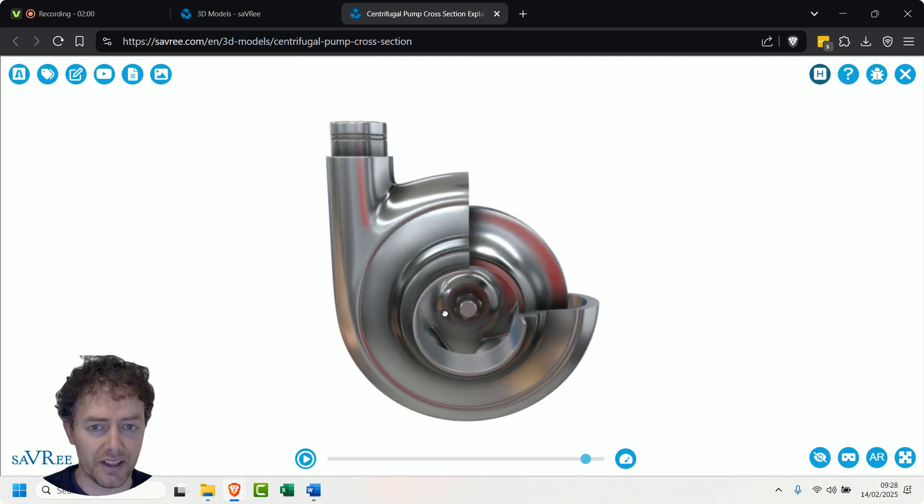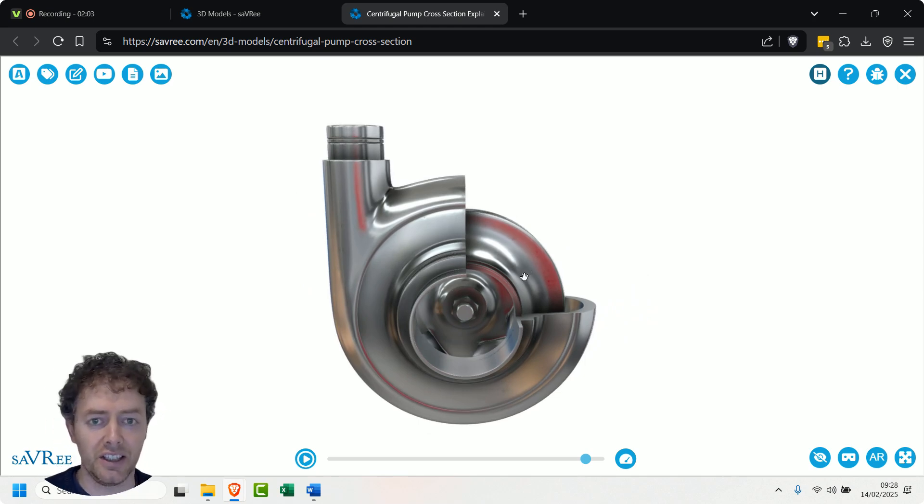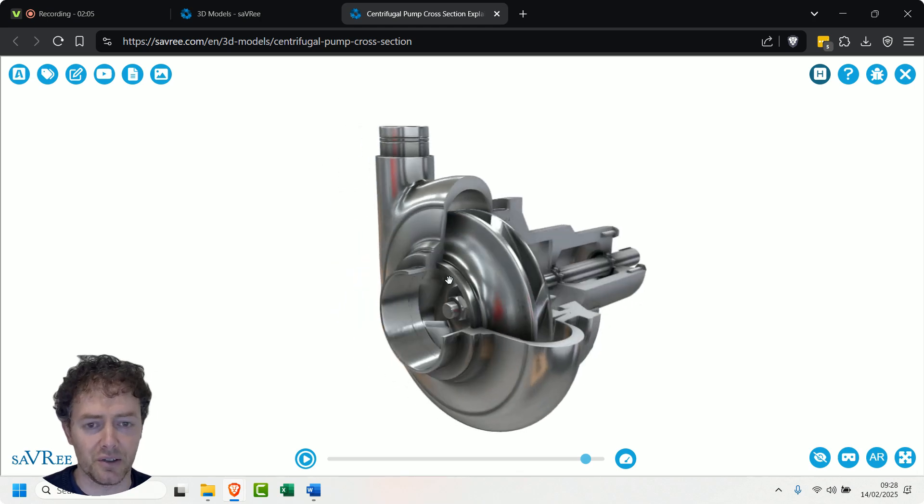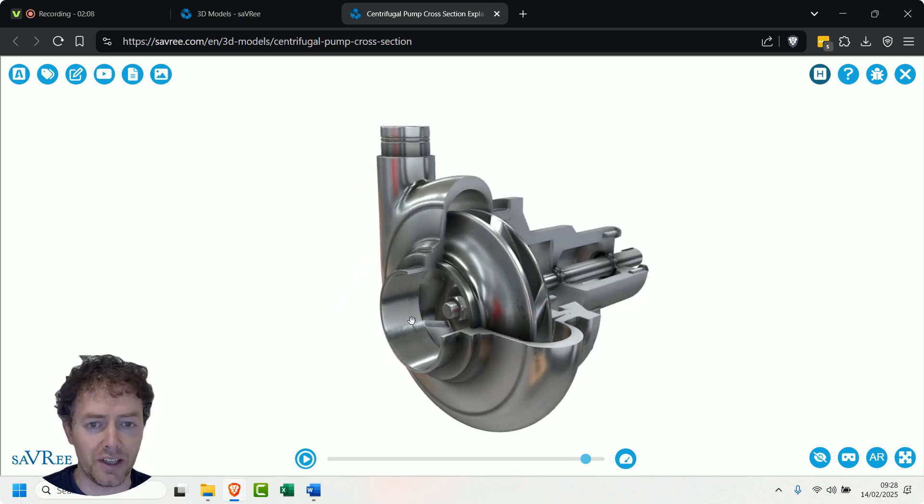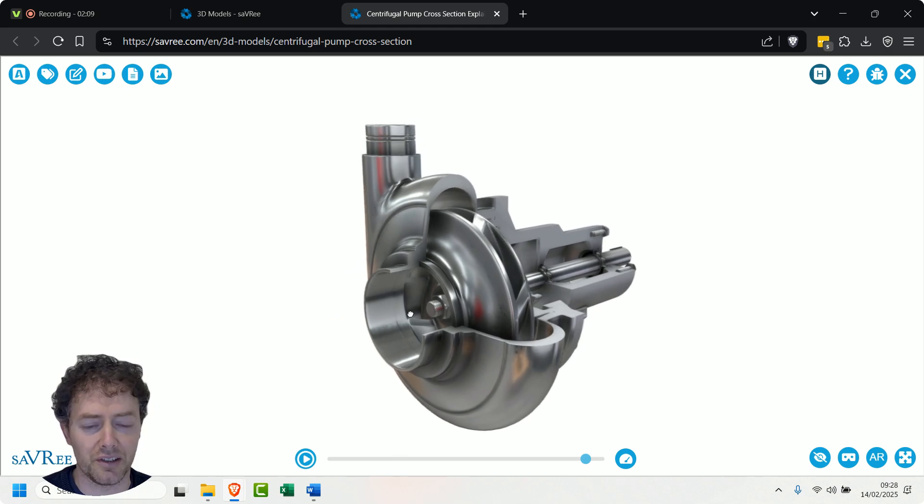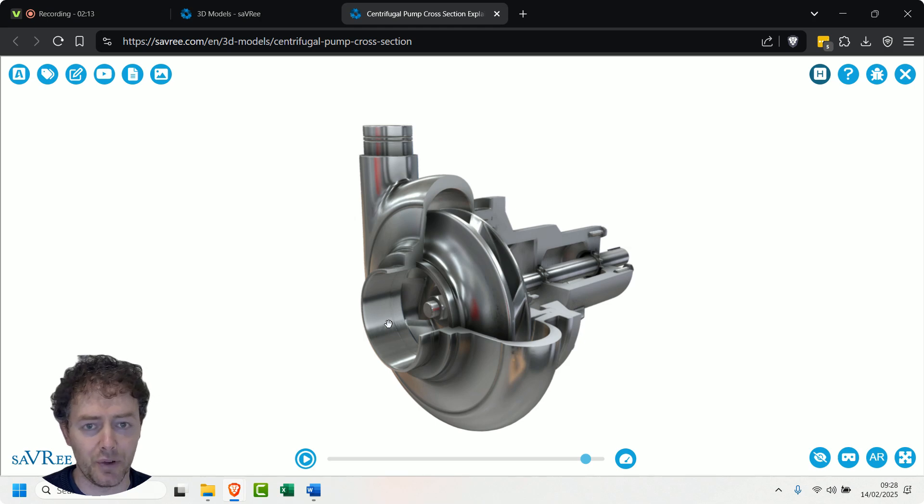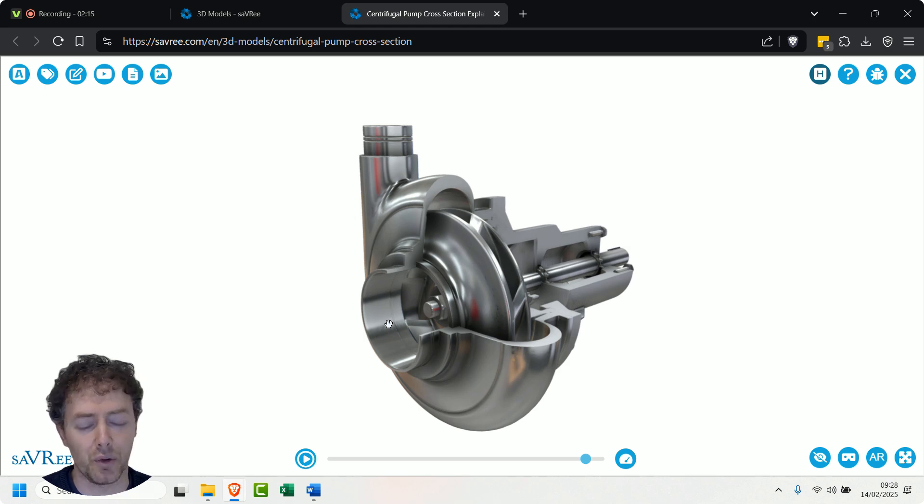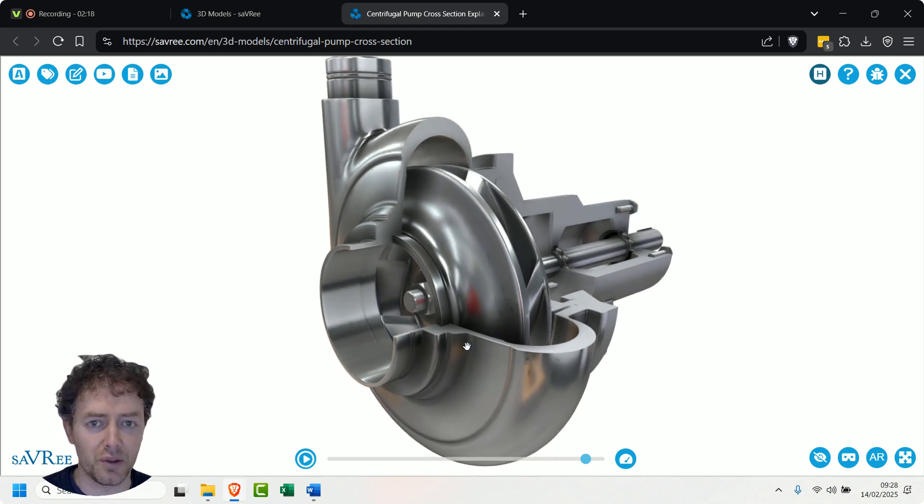The reason we've got that is because it helps us convert some of the velocity to pressure. So that's why we have it - it's called a volute casing. If you don't have a volute casing, what you'll see is a diffuser ring. But you'll typically see a diffuser ring on multi-stage centrifugal pumps, whereas volute casings are used for single-stage centrifugal pumps.